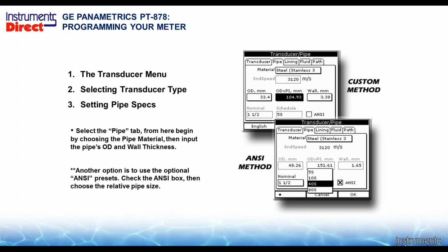After we select the right transducer, we then need to select the pipe. Across the tab here, we're going to select the pipe. We've got a drop-down menu. Today we're working with stainless, and this is set up in metric, but again, you can program the meter to read in English, whatever you want it to do. You have two choices: putting in the pipe information, or checking off the ANSI box and using the nominal dimension.